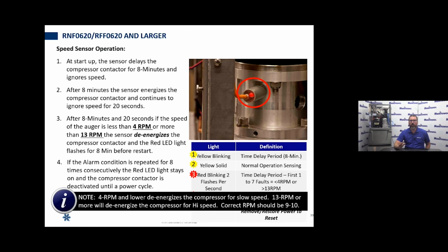What RPM are we looking for? 4 to 13 RPM, somewhere in the range of 4 to 13. 9 to 10 is ideal. At 4 RPM, if we get below that threshold, of course, we are going to lock out or shut down. If we go above that, it's also going to go into a lockout and do the same thing. So 9 to 10 is pretty standard, pretty average. That's what you'd be seeing.